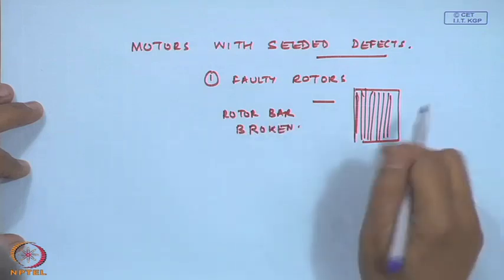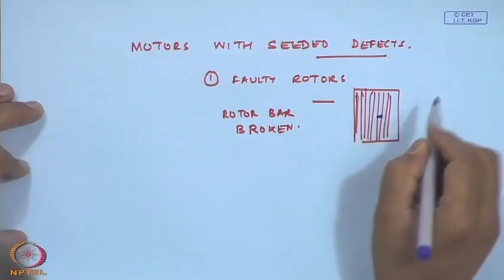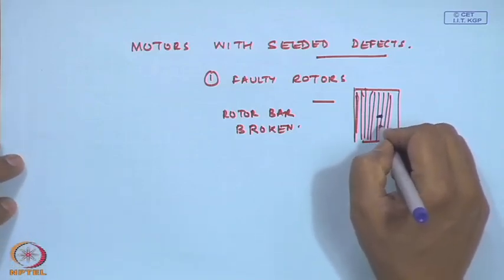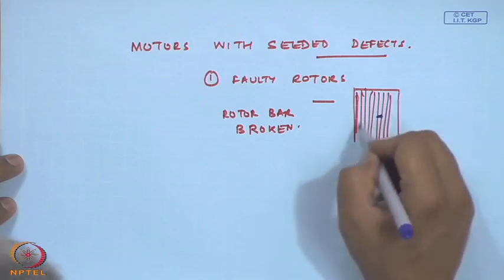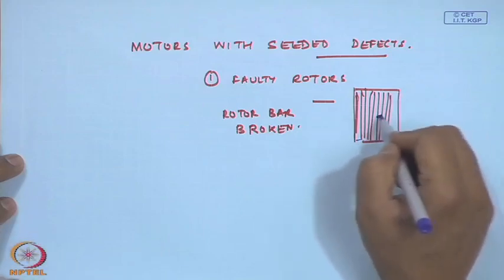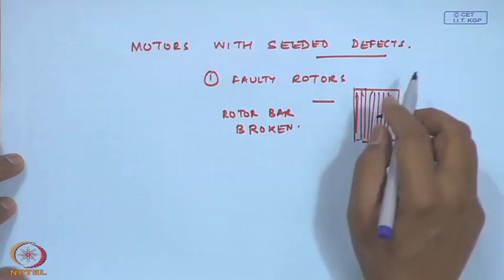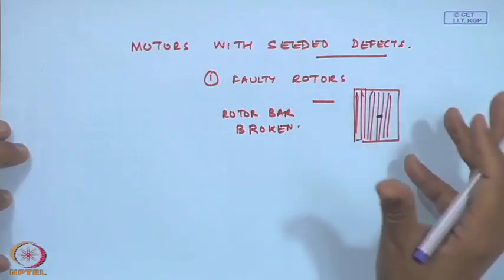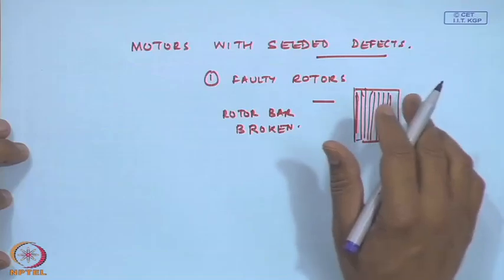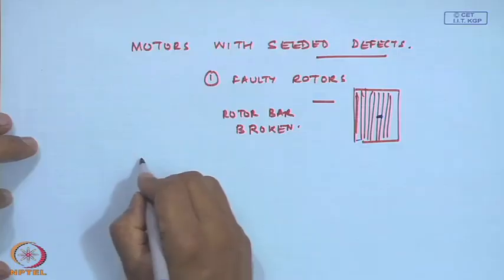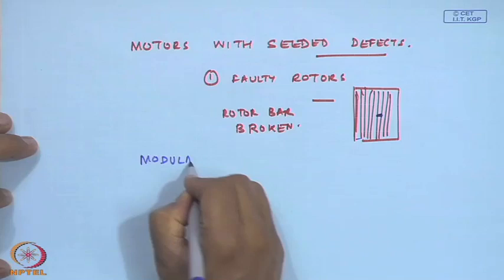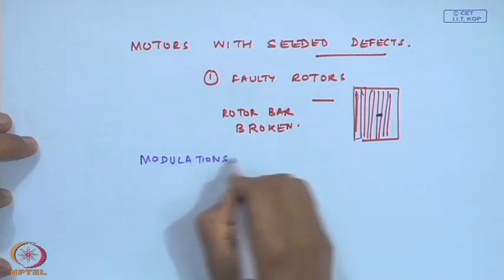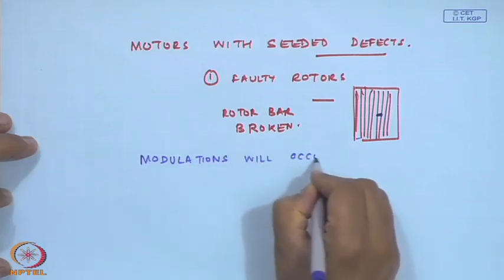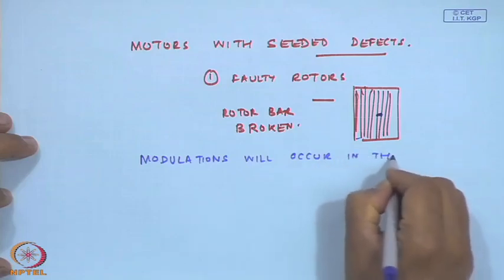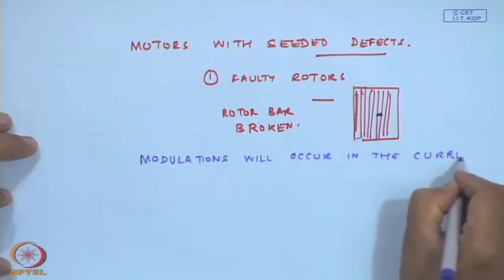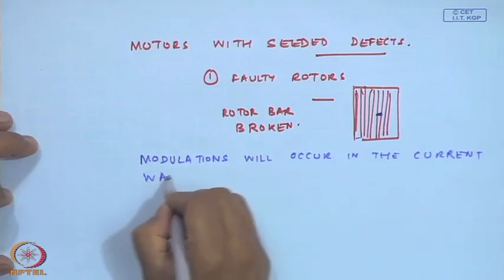What happens if one of the rotor bars is broken? Okay, the current which is supposed to flow through this conductor is not going. But to balance the load, the current in the other conductors is going to increase momentarily. So this will give rise to an unbalanced torque, and because of this torque, you will see modulations will occur in the current waveform.